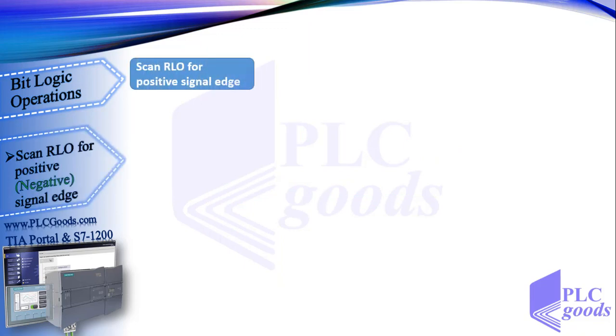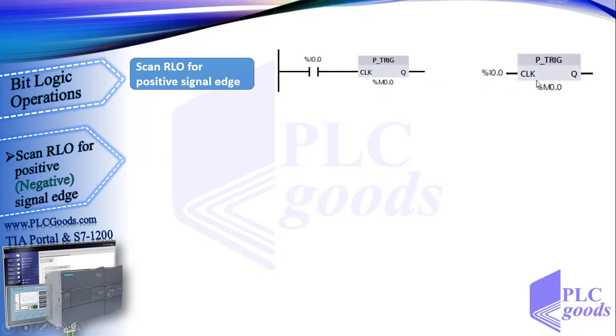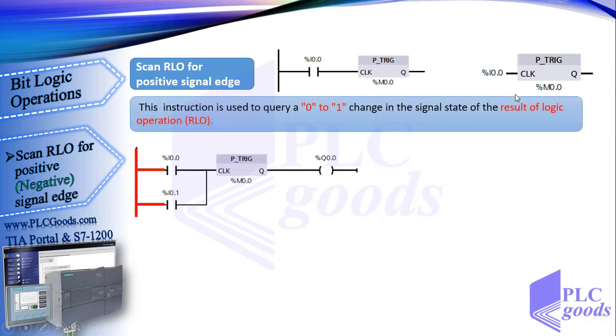Now I want to explain an instruction which scans RLO for positive signal edge. This is its ladder symbol. Unlike the previous instruction, this one only needs a memory address to work correctly. This is its FBD symbol. This instruction is used to query a zero-to-one change in the signal state of the result of logic operation — the RLO. So when either I0.0 or I0.1 is activated, the RLO changes from 0 to 1.